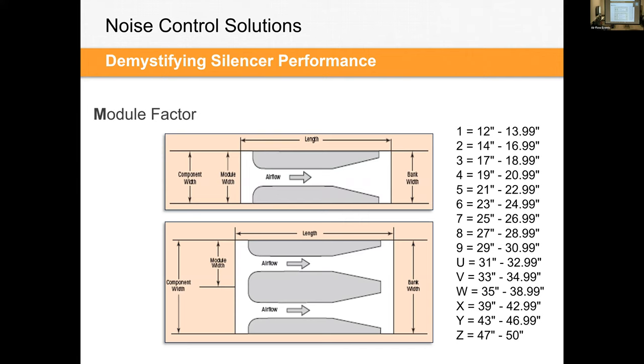So theoretically, that shouldn't change performance because you've got the same amount, whether you built it in two sections or one big section, it shouldn't change the performance, should it? It shouldn't. In practicality? And it doesn't. So for example, if this was 12 inches wide and this was a one module factor, and this was 24 and this used that same one module factor, these would perform equivalently. It would be the same overall spectrum of sound attenuation. You'd have just two of those modules in one.